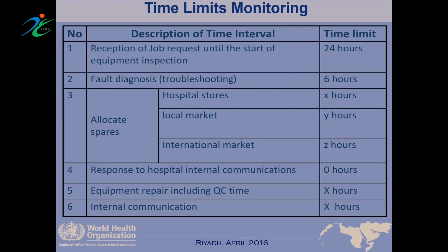This is also another example on the time needed in a particular hospital, that they have to monitor and see what the response time was to respond to a faulty equipment report or pending job order. In some hospitals it's 24 hours. Then they look at how much time it took to allocate the spare parts. Was it available in stock? So all those kinds of data, it's important that you are able to collect, for you then to decide where the gaps are, where I have to improve myself.